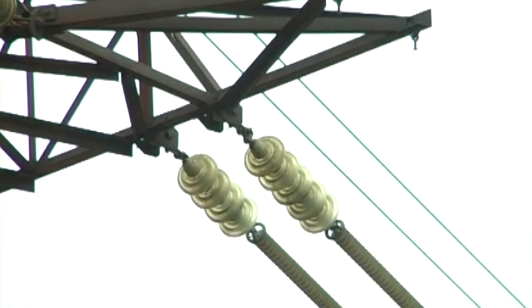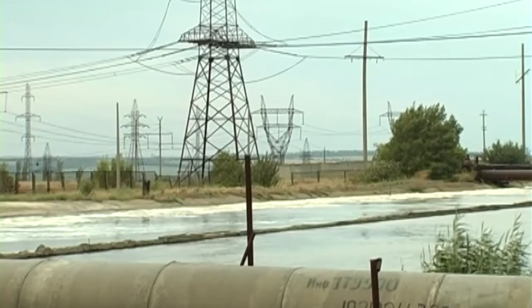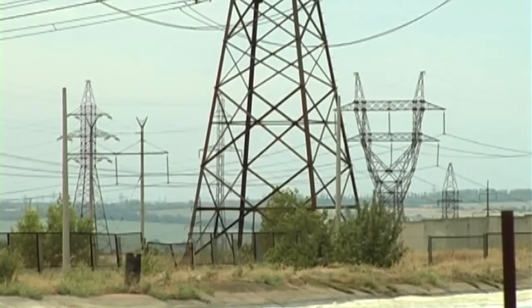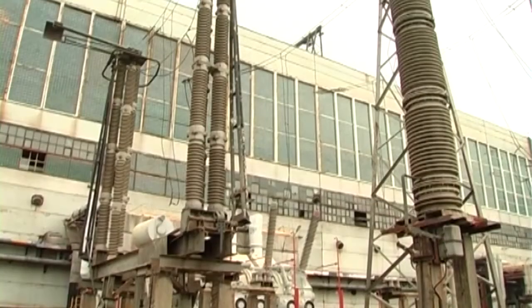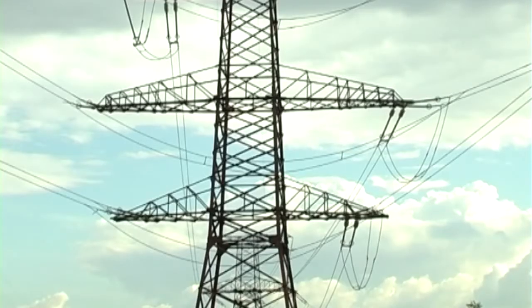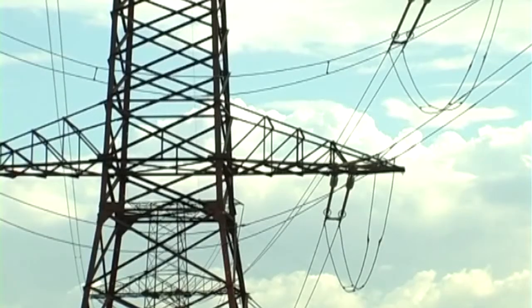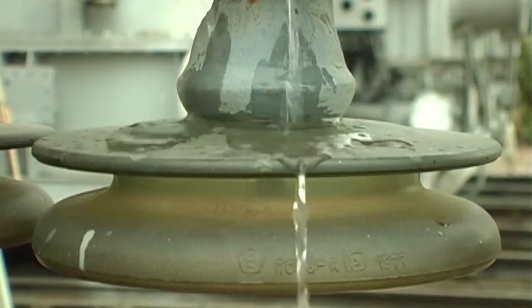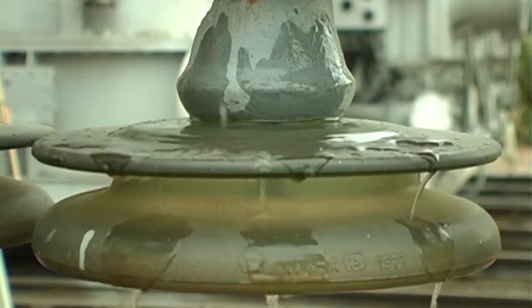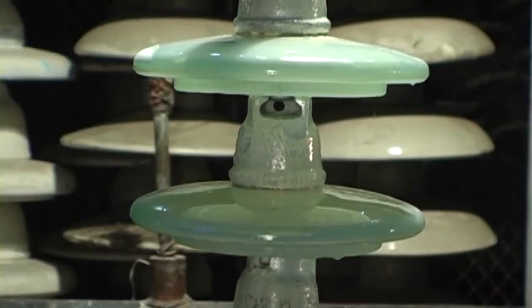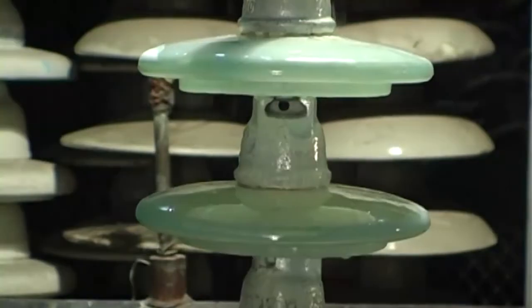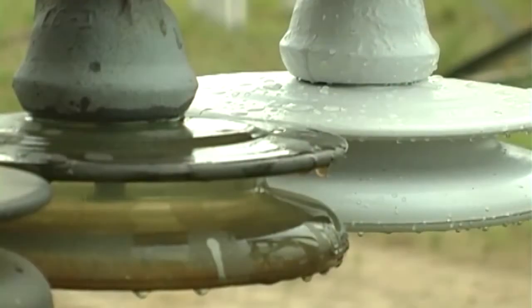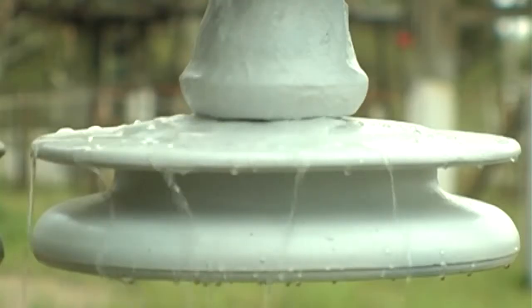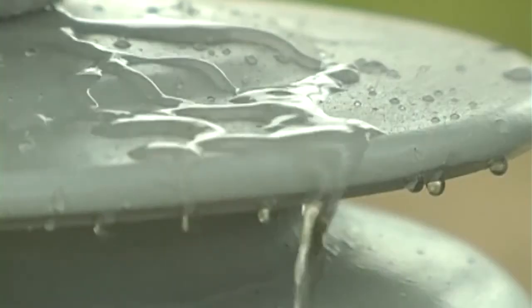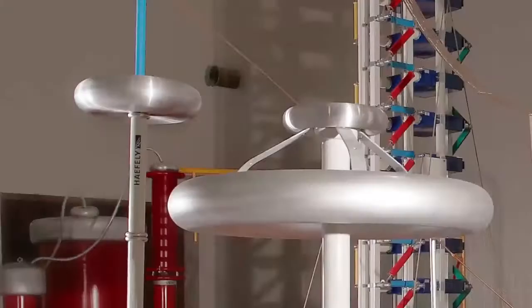Sometimes non-soluble deposits greatly outweigh the salt deposit levels that accumulate on the exposed insulator and metal surfaces. Under humid conditions and when in contact with metal, this non-soluble dust can lead to accelerating metal corrosion. Usually dry insulators don't flash over, even if they are highly polluted. However, affected by rain or condensation on the polluted surface, a partial discharge may occur. The degree of discharge activity depends on the type of the surface, whether it is wet and forms a continuous water layer, or it is waterproof due to its qualities.